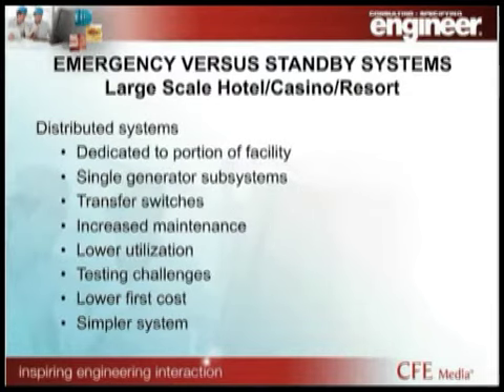So when we look at distributed systems, again, it's dedicated to a portion of the facility. It's a single generator subsystem. You've got transfer switches involved. It's actually increased maintenance, because now you've got multiple locations you've got to go to test and maintain the equipment and the transfer switches. From a loading standpoint, one of the things that makes it a little different is you actually get lower utilization on your engine typically, because now you're doing a calculation for a portion of the building. You're not getting the benefit of an aggregate diversity that you would take over the entire property. So you end up with your generators being a little bit lighter loaded.